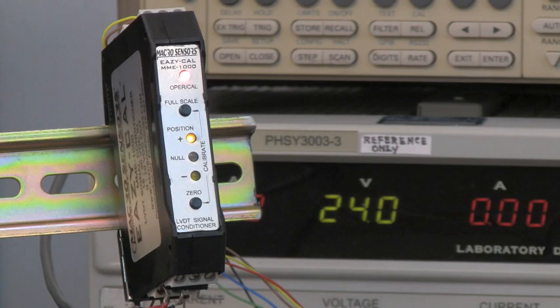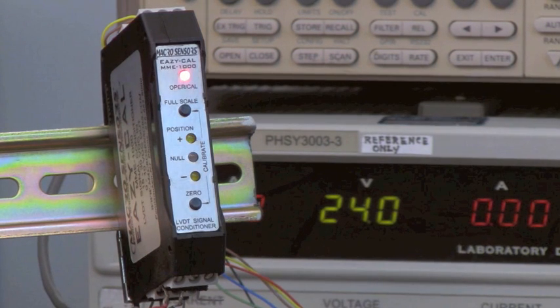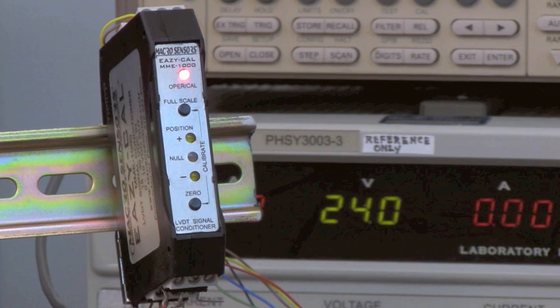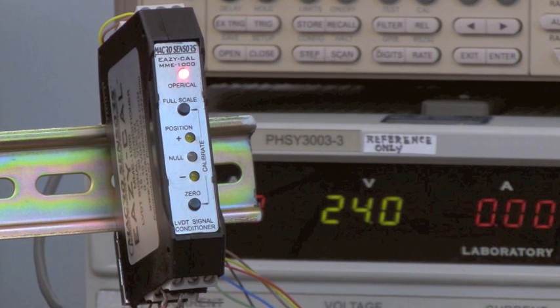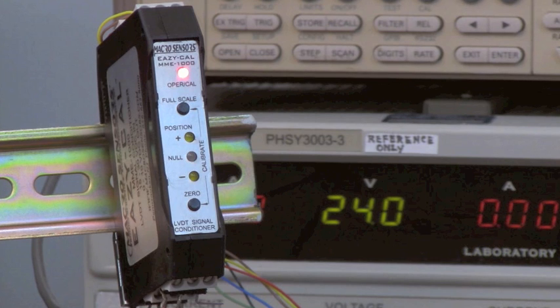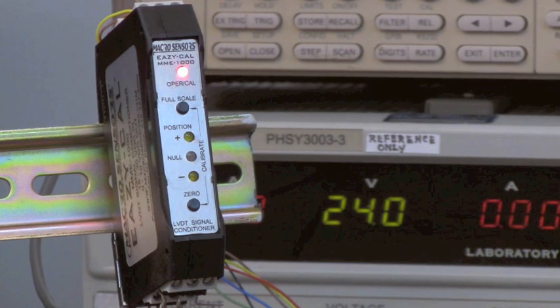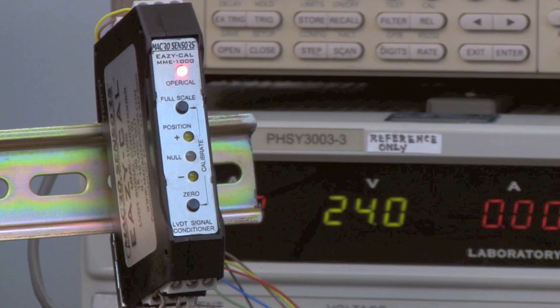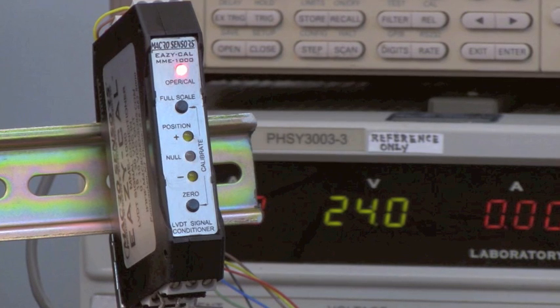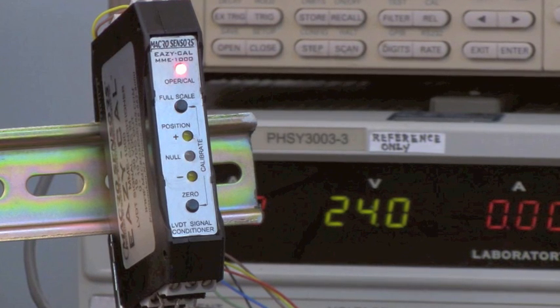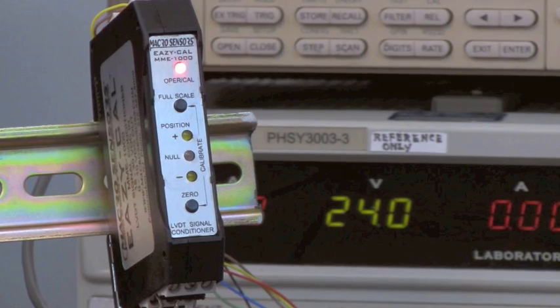It is important to note that once the calibration procedure has been initiated, an internal timer has started a countdown and will allow 90 seconds for completion of the calibration routine. If it is not completed within the allotted time, the EAZY-CAL will automatically revert to normal operation mode and its previous calibration settings. You also have the option to manually abort the calibration sequence at any time by simultaneously depressing and holding the 0 and full scale buttons for 3 seconds. This will also cause the EAZY-CAL to revert to normal operation mode and its previous calibration settings.